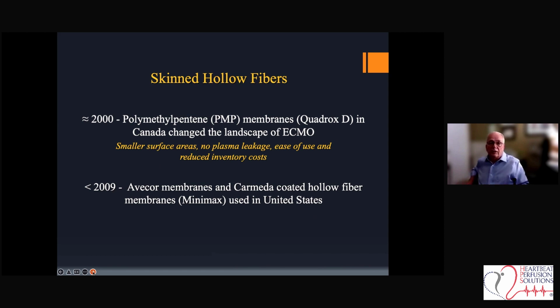So when I'm talking about the skinned hollow fiber technology, these PMP membranes, they came over into Canada first, coming over to North America from Europe. They came over in the form of the Quadrox D membranes, and that was around the year 2000 when they came in. Once they came in, we found that they had smaller surface areas, no plasma leakage. They were easy to use and prime, and they dramatically reduced the inventory costs of stocking membranes for the adult and pediatric populations. Here in the United States, the use of these polymethylpentene membranes really didn't come into the U.S. until around the year 2009.